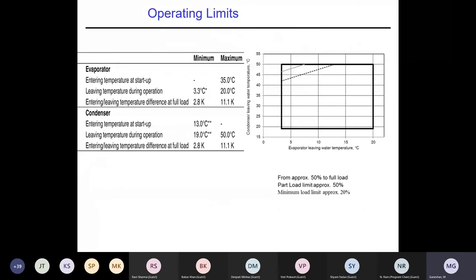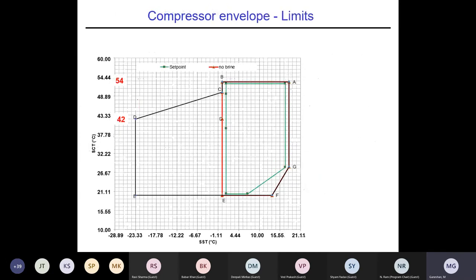For every compressor, whenever it is designed, they always give a graph, and operation should stay within it. If the operating temperature ever goes beyond this, we are automatically making the compressor operate under higher overload conditions. This is why we say keep the record. Why a logbook? Whenever manufacturing engineers or service engineers come, they can see from it that this has gone beyond the limit, and then try to bring it back to the normal level. We should know this too. This is the compressor envelope, and operation should stay completely within it.